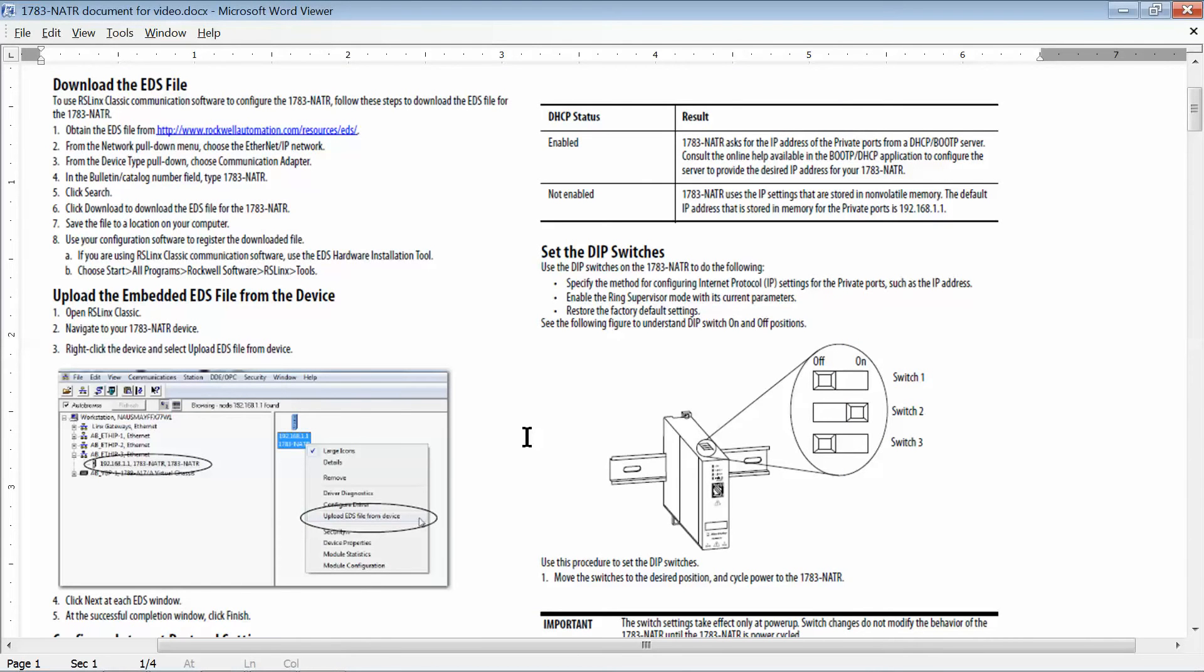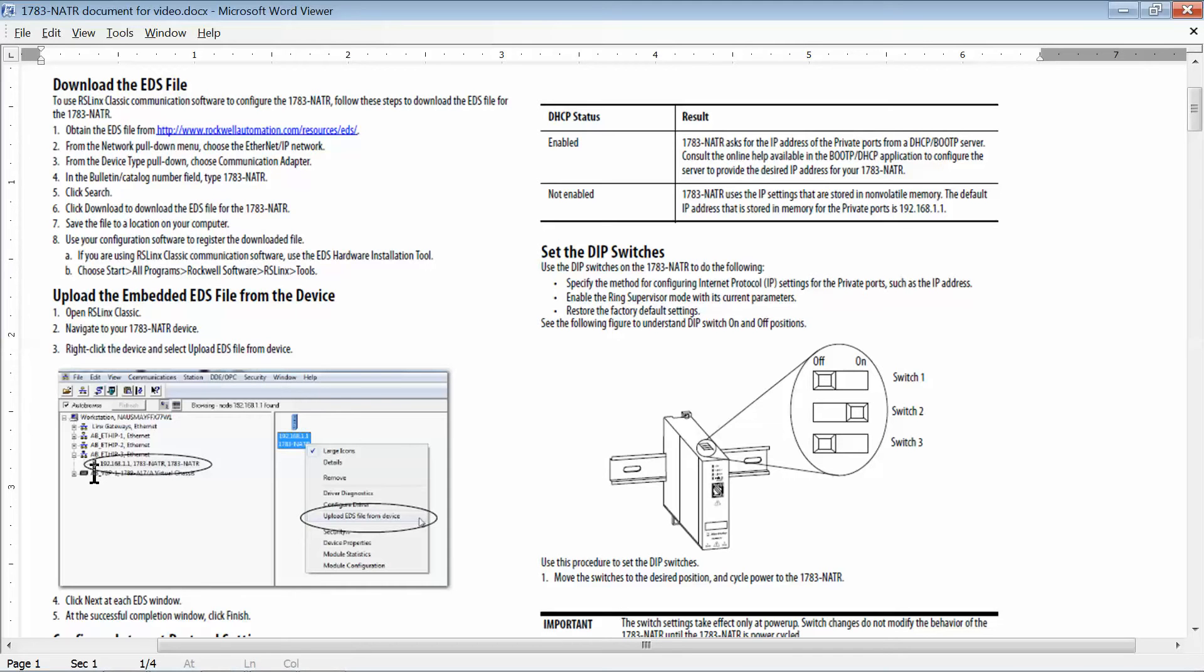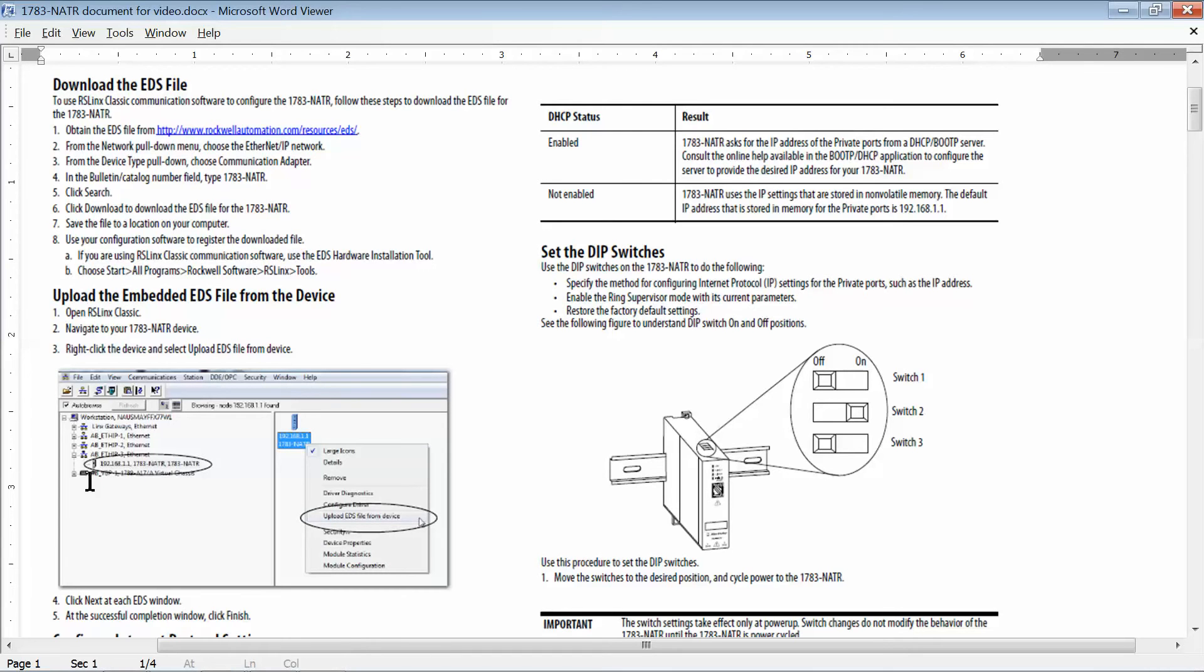Now, once you've got the IP address for your laptop set on the same subnet as the NATR, there's a couple of things you can do. If you go in with RSLinx, if you're using Rockwell, when you set up your Ethernet driver to use the same subnet as the NATR, what you'll see right here, you'll see something that says 192.168.1.1. That is going to be your NATR device. When you do this initially, that might be a question mark right there. And then what you can do is just right click on that and upload the EDS file right from the device. And then it will upload the device EDS file for you and then you'll have a nice picture in your RSLinx.